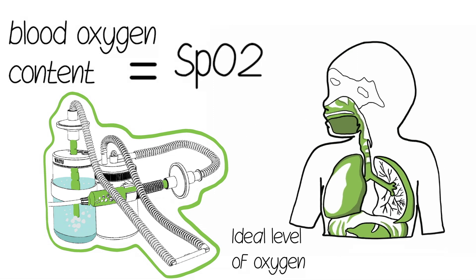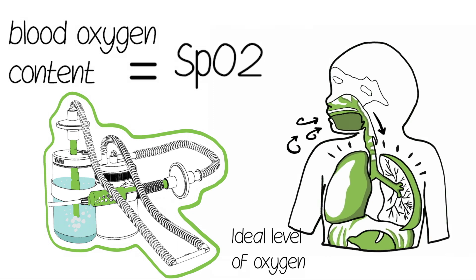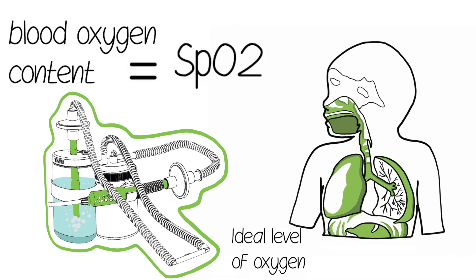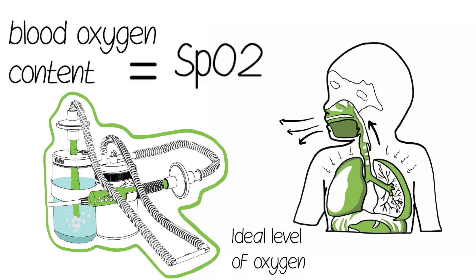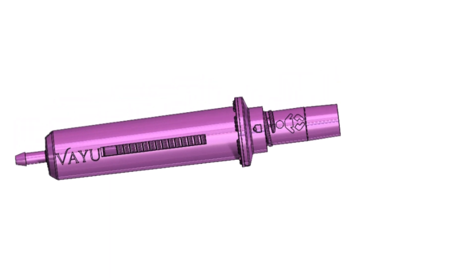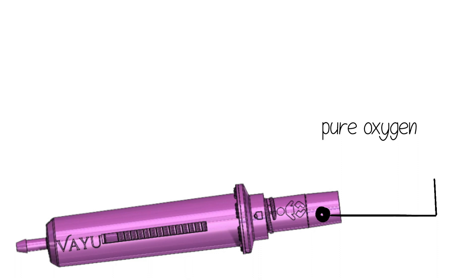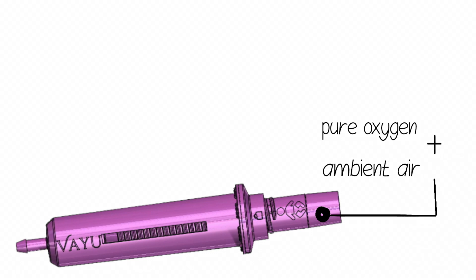The VAYU bubble CPAP system is unique in how it controls the FiO2. In the VAYU system, FiO2 levels are controlled by a blender which mixes pure oxygen with ambient air using the Venturi effect.